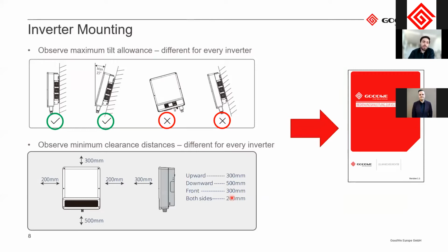When you mount the inverter, please also observe in the manual, as I said before, the maximum tilt angle allowed. And this is also a bit different for every inverter. Usually you're not allowed to tilt it sideways or to the front, but it should be installed upright. For the ET, for example, you can install it slightly backwards, and this is maximum 15 degrees backwards then. And this is to ensure that the cooling system works properly.